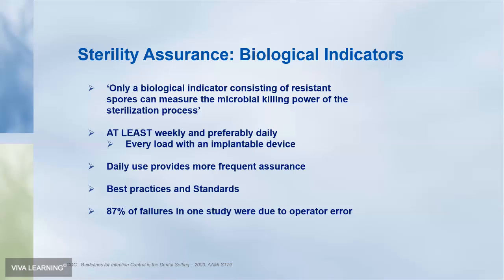Biological indicator use is also best practices and standards. Now, why would it fail? Inherently, we probably want to think it's the spore test that failed. But in fact, many studies have shown that operator error is a major cause of failure. In one study, 87% of failures were due to operators not operating the equipment correctly.